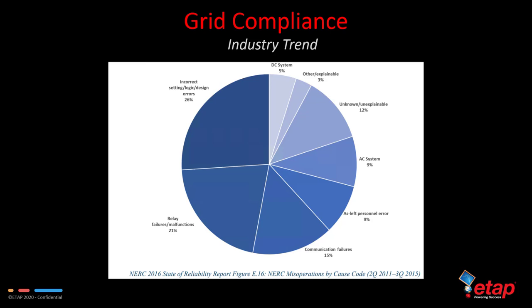Protection system design usually considers two aspects of reliability: dependability and security. As the speed and complexity of operations continue to escalate, the ability to stay in compliance becomes directly determined by effective system-to-system communication between many departments. It's easier said than done if your operations are vast. When a protection system misoperation occurs, the resulting system performance will depend in part on the type of misoperation that occurs and the characteristics of the power system on which the protection system is applied. There's generally a trade-off between dependability and security. And of course, improving one typically degrades the other.